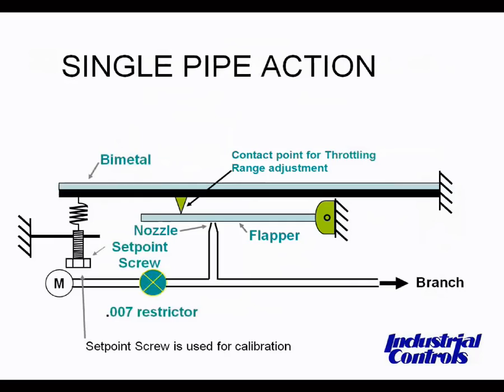We'll talk a little bit more about how a single-pipe thermostat works. This slide shows how a one-pipe thermostat operates. As the bimetal senses a temperature change, it causes the flapper to move, thus increasing or decreasing the nozzle opening. If the nozzle is completely closed, the pressure in the branch line will increase until it is the same as the main pressure. If the nozzle is open far enough, air in excess of the amount coming through the restrictor is bled off, causing the pressure in the branch line to fall to zero. Thus, the thermostat may be thought of as a pressure regulator, varying the pressure in the branch line in direct relationship to the temperature at the bimetal. One-pipe thermostats are very low-volume devices and should only be used with small actuators and valves. The branch line should never be very long — the control device should be no more than 20 to 30 feet from the thermostat. These thermostats have a dial set point and adjustable throttling range.